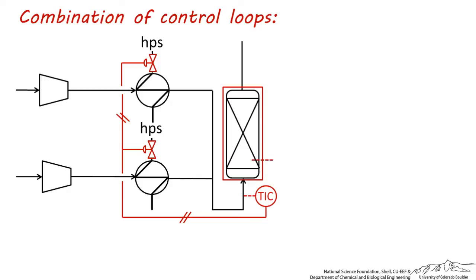The temperature should be read from inside the reactor, sent to a temperature indicator controller, which then should control the flow rate of cooling utility going through the jacket to either absorb more or less heat. This is probably the best way of showing that the utility going through the cooling jacket is being controlled. However, if you'd like to add a notation, which makes it more conspicuous, you can state the utility used next to the control valve.